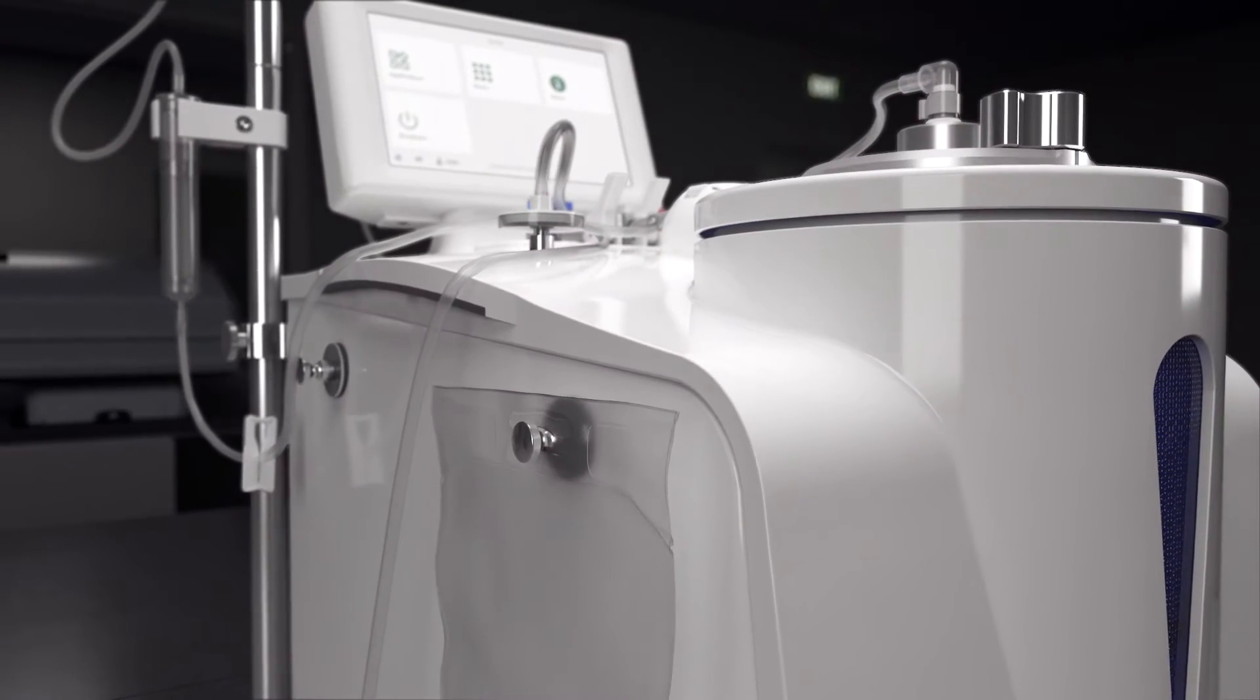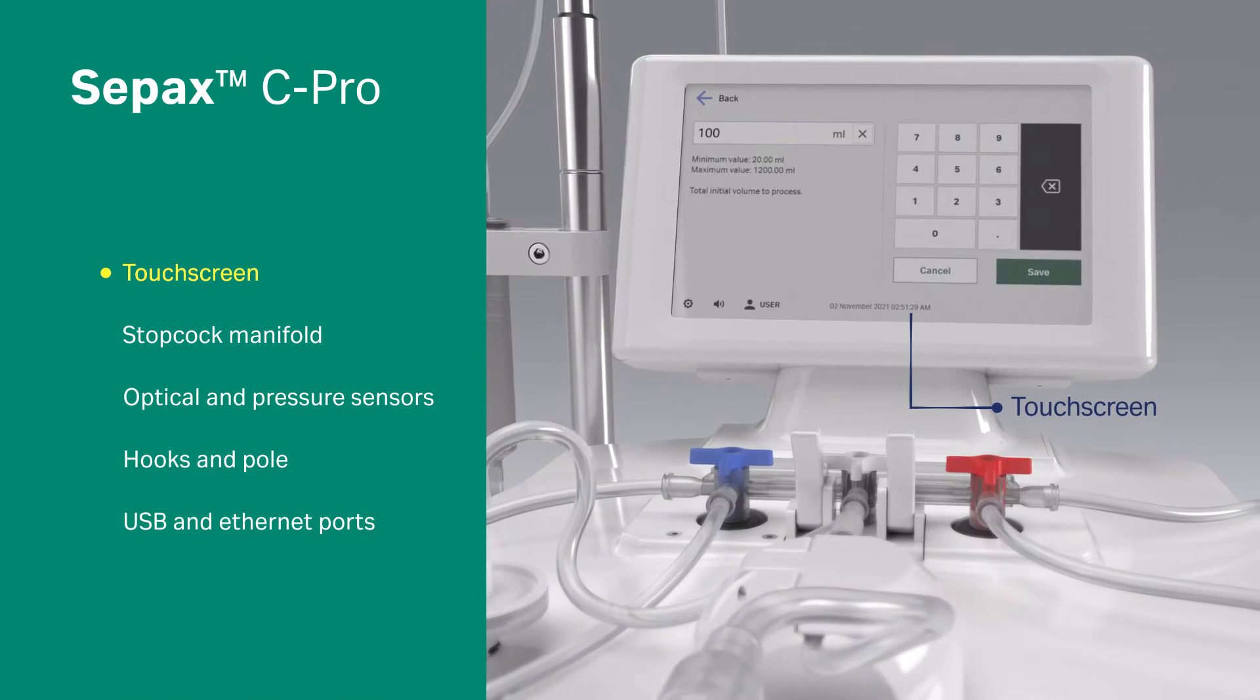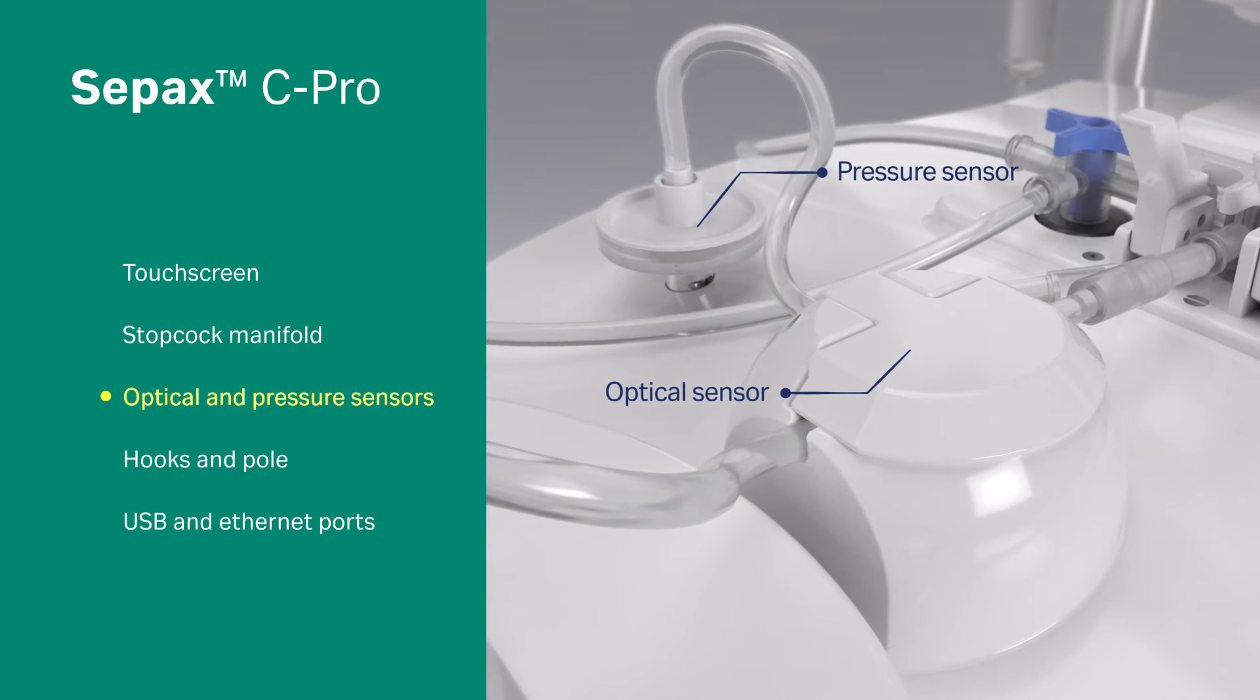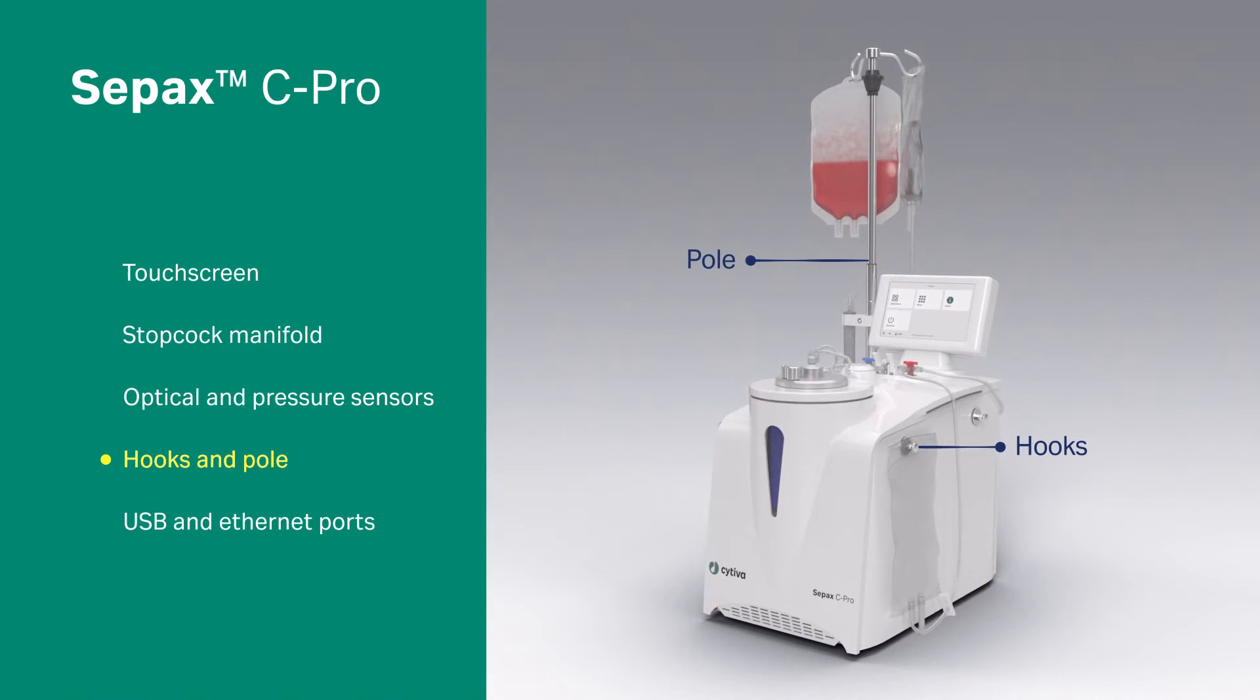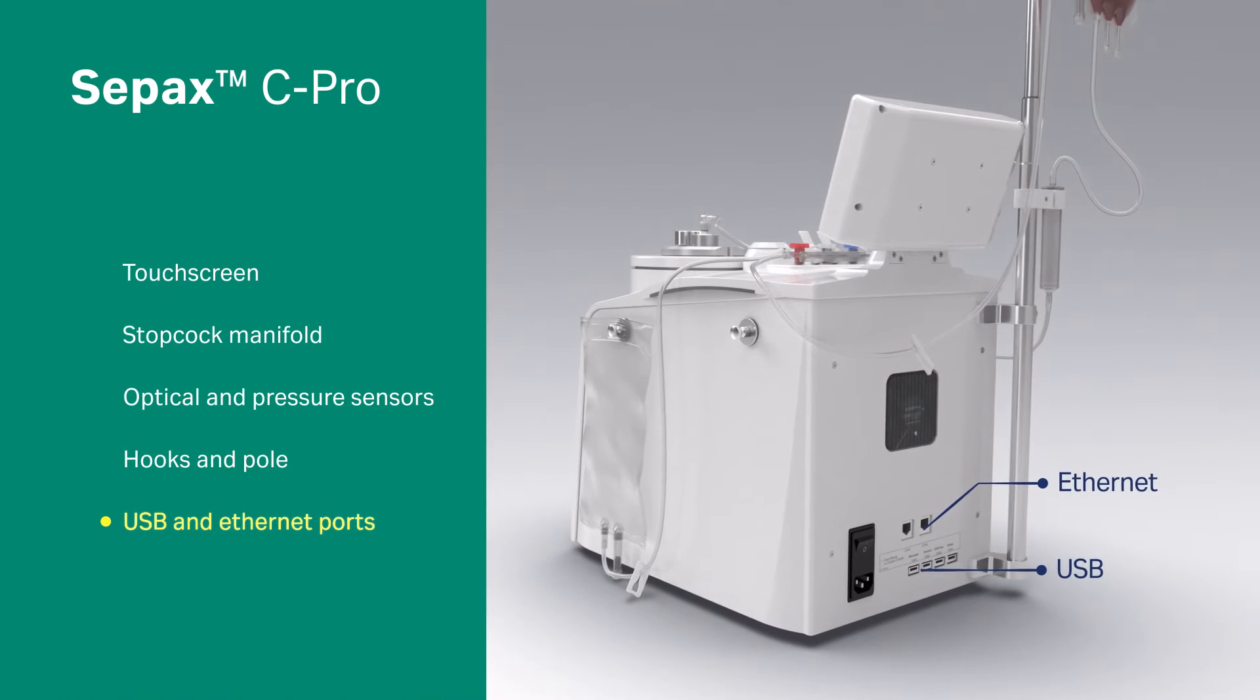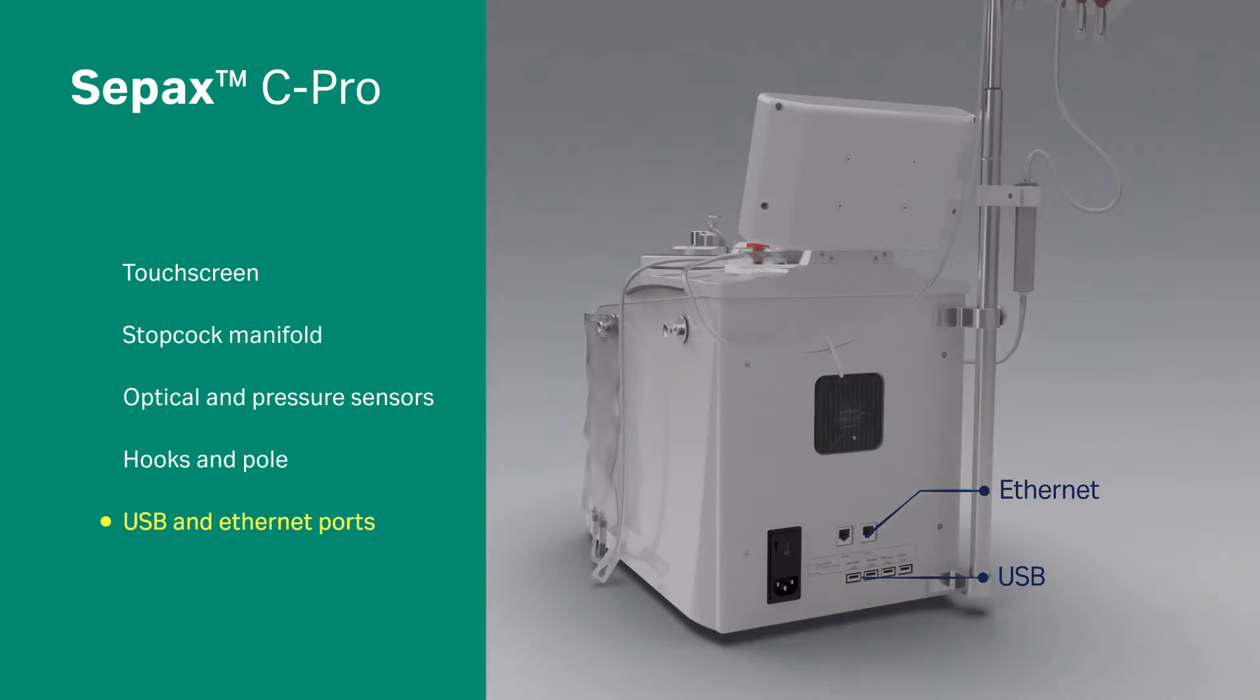The main features of Sepax C-Pro System include touchscreen-based user interface, stopcock manifold for controlling the flow path, optical and pressure sensors for process monitoring, hooks and pole for hanging process bags, and USB and Ethernet ports that provide connectivity and traceability using a barcode reader or chronicle automation software.